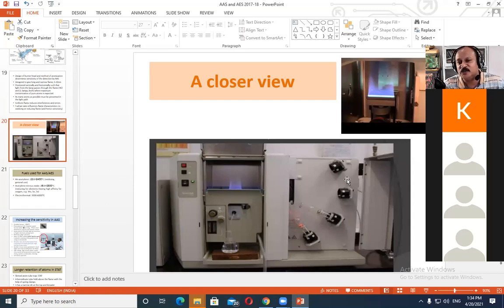But what I wanted to show you is that in the earlier instrument there was a single lamp attached, and for every different metal we had to remove the lamp and replace it with another. In this model there is a turret assembly where we can put different lamps together. If these lamps are often used, we only need to give the command in the software, specify which lamp is to be used, and that lamp will come into the proper position.